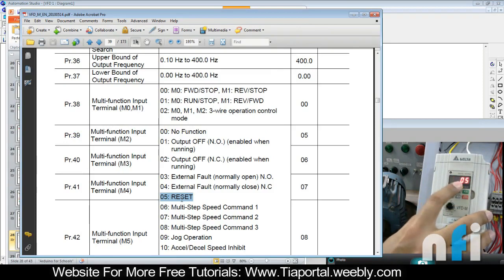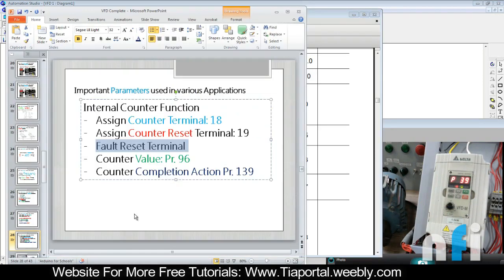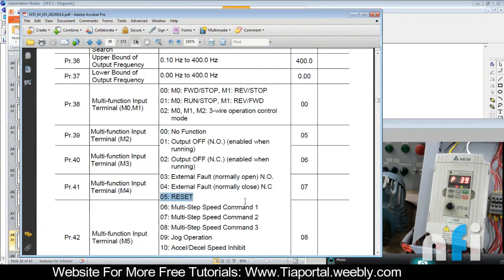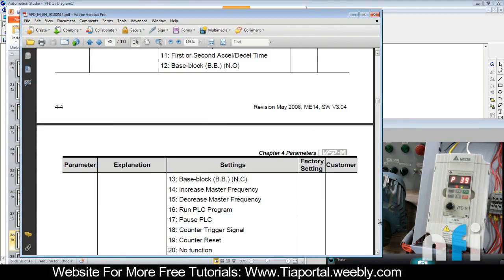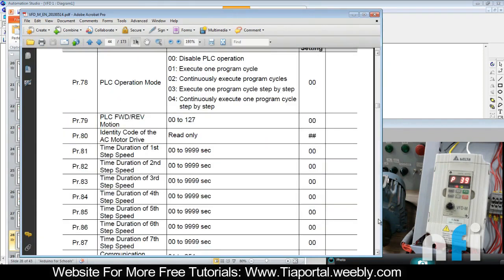Then you have counter value - how much value you need to count, how much value you need to evaluate so that beyond that there should be a fault. So that comes in parameter 96. Parameter 96 says counter countdown complete - this is the value which we need to put here.